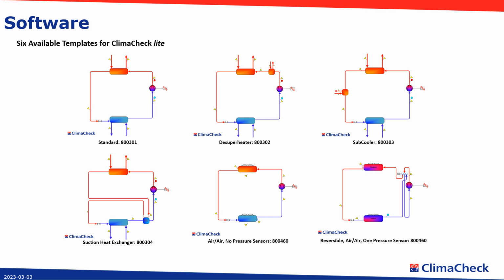Here you can see all the available templates for ClimaCheck Lite. The first one being a basic system, the second one with a de-superheater, the third one with a subcooler, the fourth one with a suction heat exchanger, and the fifth one is an air-to-air system that requires no pressure sensors, and the last one is a reversible air-to-air system that requires only 1 pressure.